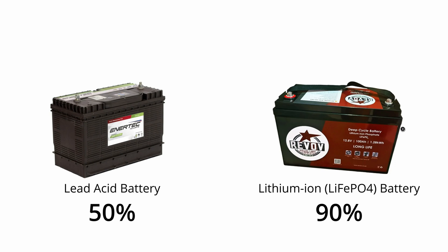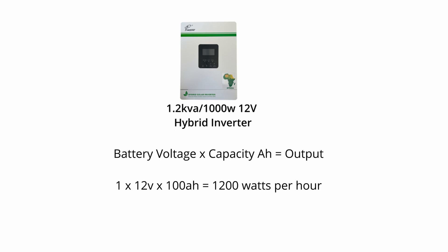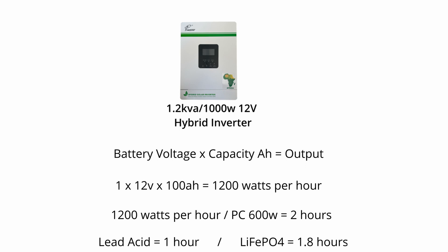depending on the manufacturer, you can go down to about 90% of the battery's capacity. For example, with one 12 volt 100 amp hour battery you'd be looking at 1200 watt hours. If you're running a PC that uses 600 watts, you divide 1200 watt hours by 600 watts, which means your battery has the capacity to run for two hours. With a lead acid battery it's only recommended that you run for one hour, whereas with a lithium-ion battery you'd be able to run for 1.8 hours.